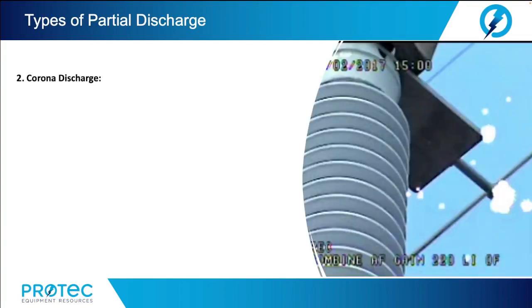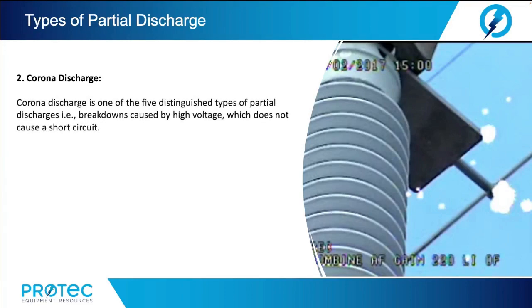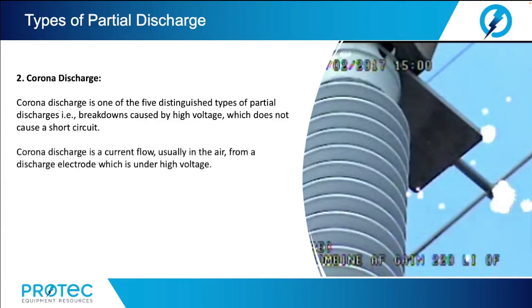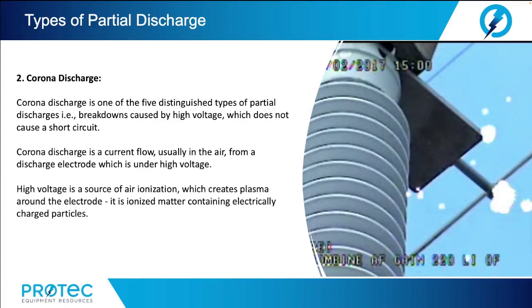Number 2, corona discharge. Corona discharge is one of the 5 distinguished types of partial discharge. Example, breakdowns caused by high voltage, which does not cause a short circuit. Corona discharge is a current flow, usually in the air, from a discharge electrode which is under high voltage. High voltage is a source of air ionization, which creates plasma around the electrode. It is ionized matter containing electrically charged particles. The resulting ions carry the load to places of lower potential.